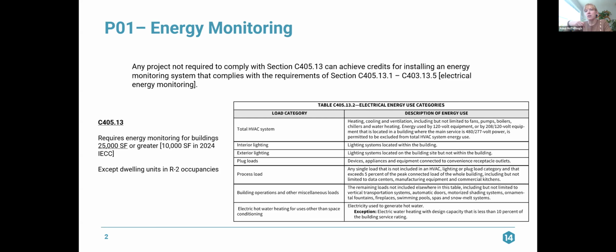Interior lighting needs to be monitored separately. Exterior lighting, plug loads, and any process loads, so anything that is not included in an HVAC, lighting, or plug load category but exceeds 5% of the peak connected load of the building, has to be monitored separately. It could be you have a data center in your building, or you have an all-electric kitchen. Those process loads need to be monitored.